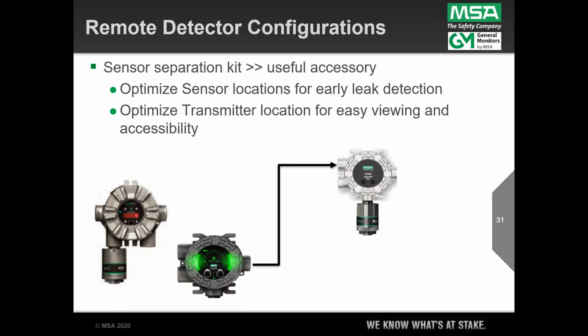From the service technician perspective, this is one of the most useful accessories for any point gas system, and that's a sensor separation kit, a remote SEP kit. And why? Because this allows the end user to put that sensor where it's going to be optimal for early leak detection. That might be high for methane, lighter than air gases, or hydrogen. It might be low for your heavier than air gas liquids, or gasoline or heptane or some other heavy vapor. But then keep that transmitter at eye level for easy viewing and accessibility.